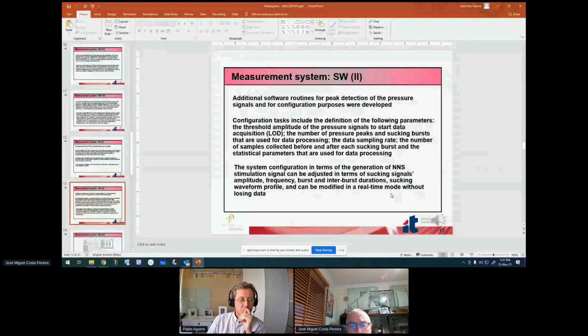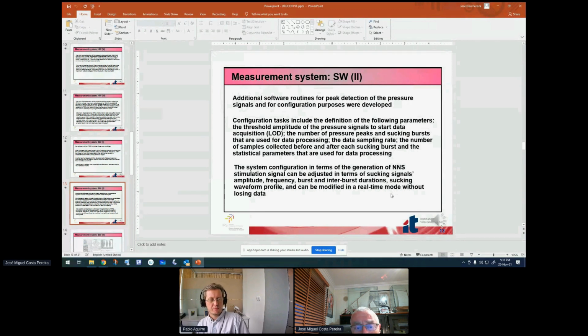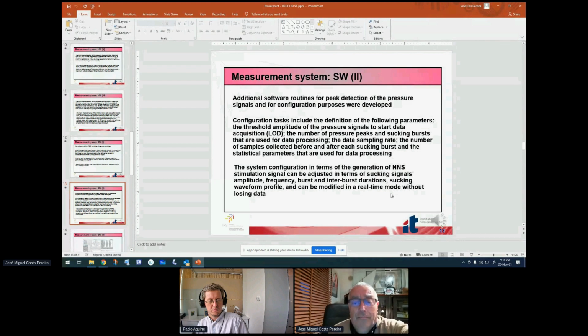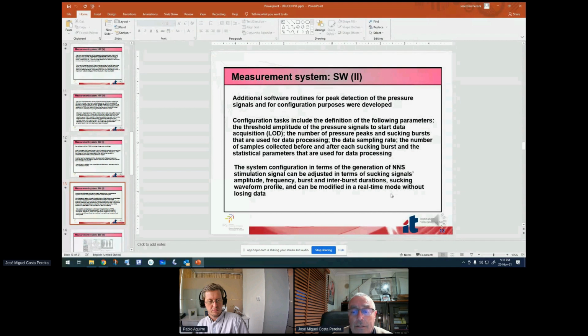Additional software routines for peak detection of pressure signals and for configuration purposes were developed. The configuration tasks include the definition of several parameters, namely the threshold amplitude of pressure signals to start acquisition, the number of pressure peaks and sucking bursts that are used for data processing, the data sampling rate, the number of samples collected before and after each sucking burst, and the statistical parameters that are used for data processing. The system configuration in terms of non-nutritive sucking stimulation can be adjusted in terms of sucking signals, amplitude, frequency, and burst and interburst duration. And they can be modified in real-time mode without losing any data.